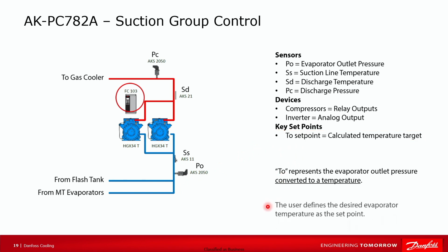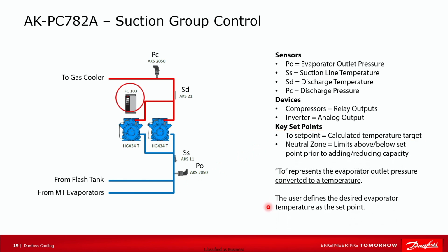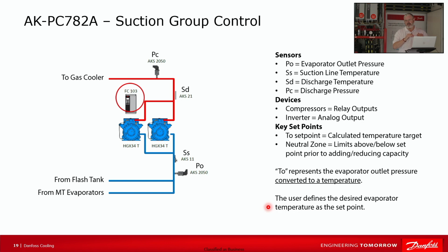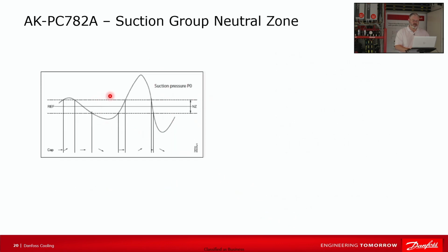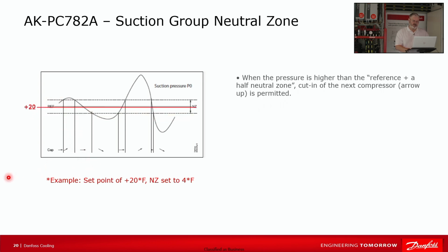And then as far as staging compressors, we use what we call a neutral zone strategy. Basically the neutral zone are limits above and below the target set point, within which you don't bring stages on and off, so that you don't chatter the compressors and short cycle the system. Our neutral zone diagram, the illustration, kind of goes like this. We've got an example here. Set point is plus 20, so that's our reference. And then our neutral zone is set to 4 degrees.